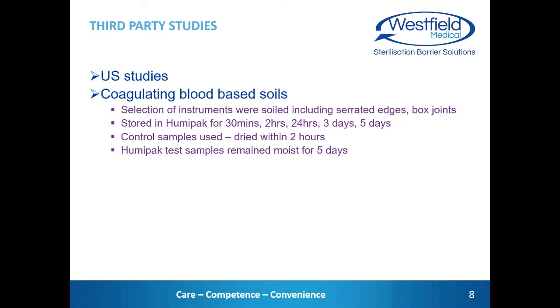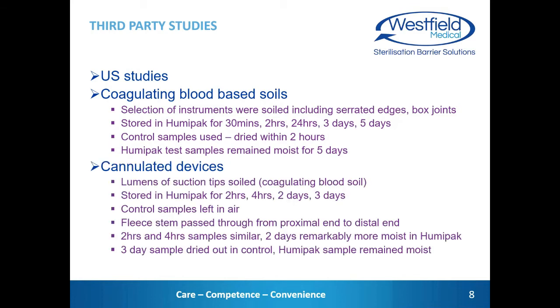The overriding result there was that after 5 days, the samples that were in HUMIPAK remained moist, whilst the others dried out very rapidly within the first couple of hours. They then had a look at the effectiveness with cannulated devices. On this one, they looked at it for up to 3 days. Soils were enclosed in a lumen. These took longer to dry out, but in general, if you do get soils drying out inside a lumen, they're much more difficult to remove. And again, on this, the samples in HUMIPAK maintained the moisture levels in the soil, whereas the control samples didn't.